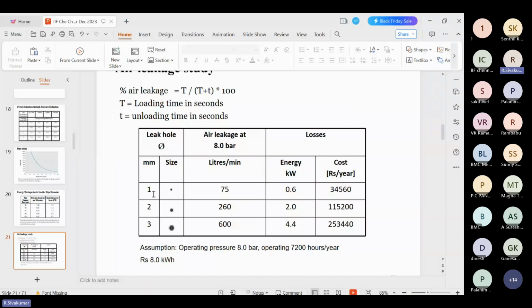For every 1 mm hole, leakage at 8 bar loses 75 liters per minute. For a 3 mm hole, it loses 600 liters per minute, and the equivalent energy loss is 4.4 units, whereas for 1 mm it is 0.6 units. The cost is equivalent to 34,560 for 1 mm and 2,53,440 for a single 3 mm leakage at 8 bar pressure. We are losing around 2,53,440 rupees in a year. Consider this assumption: operating pressure is 8 bar and operating hours are almost 7,200 hours in a year.